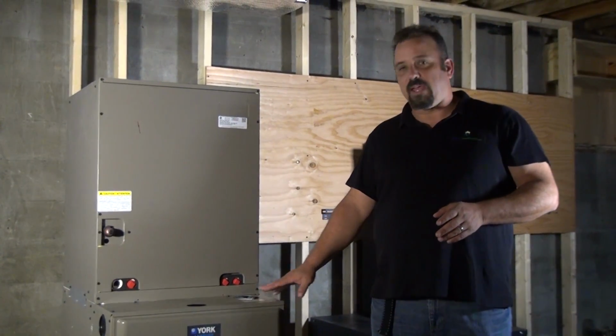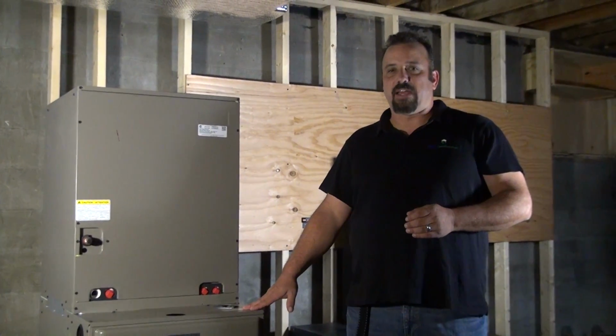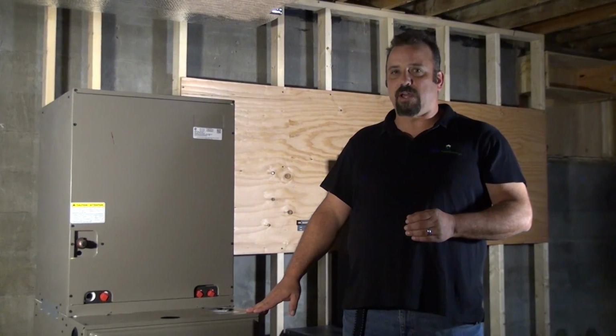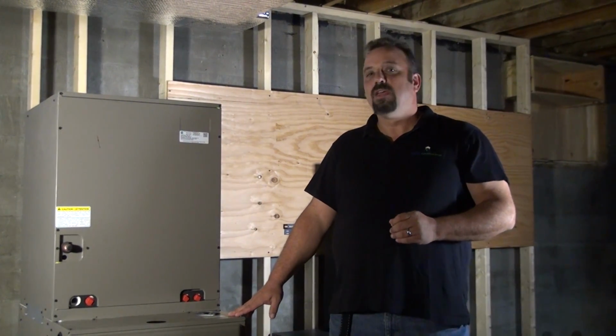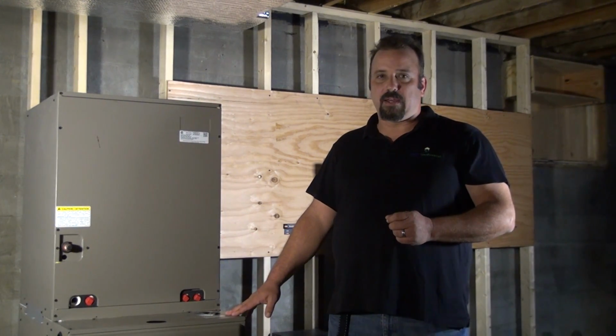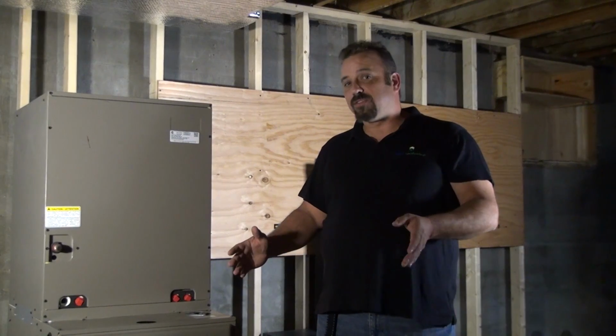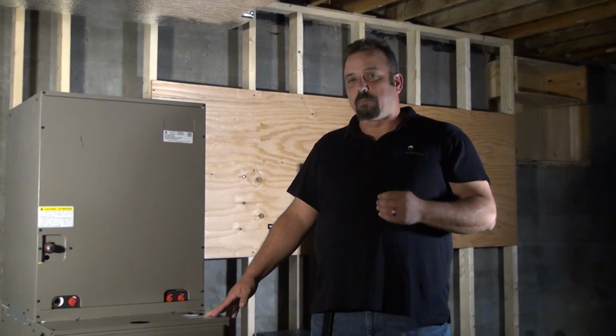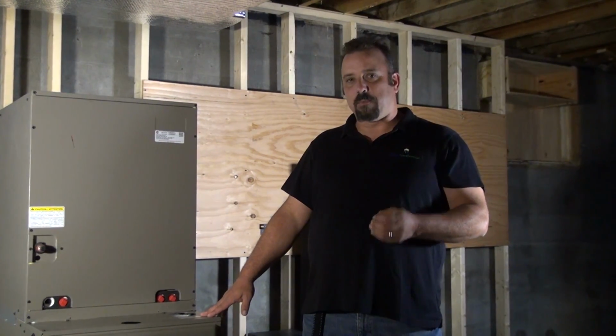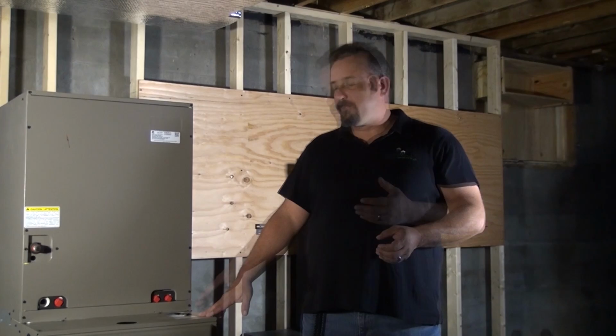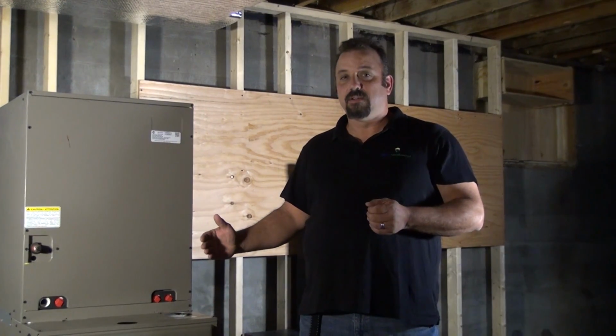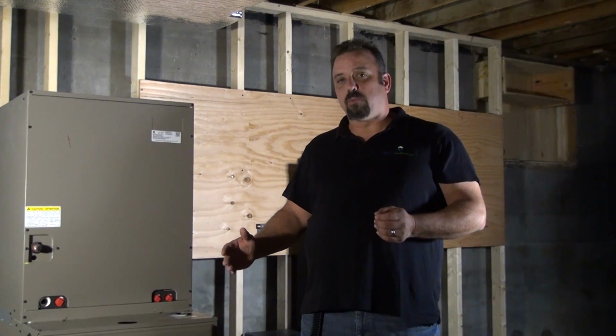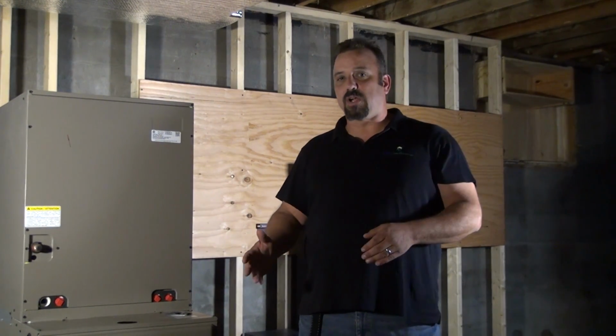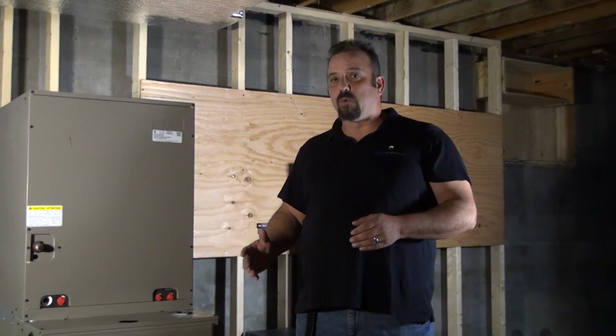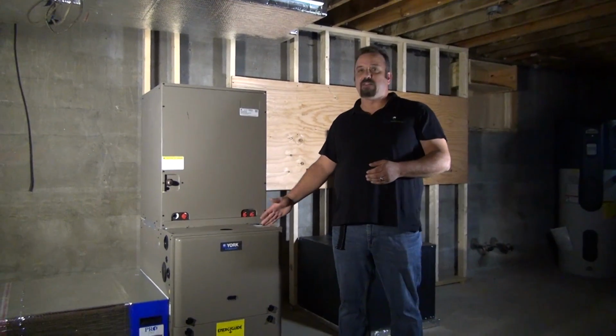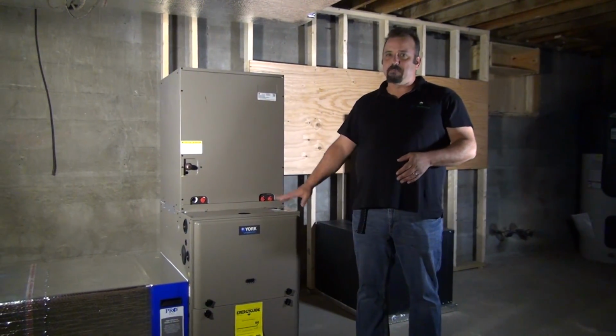But the better benefit to this system, and why this is being done here, is generator sizing. For those of us who live here in New Hampshire, we know that power outages have been very prevalent in the last 5 to 10 years. When you install a geothermal heat pump into a home and you need a backup generator sized for that geothermal heat pump, the problem is you need a very large generator because the compressor runs at what they call a very high locked rotor amperage, thus creating a need for a very large generator to run the house. So in this particular application, when there is a power outage, the generator can be sized much smaller, which is much more cost effective to handle the whole house, and the generator will now work with this gas furnace. So when you lose power, the gas furnace can run off your generator. So a lot of benefit to going with the system.